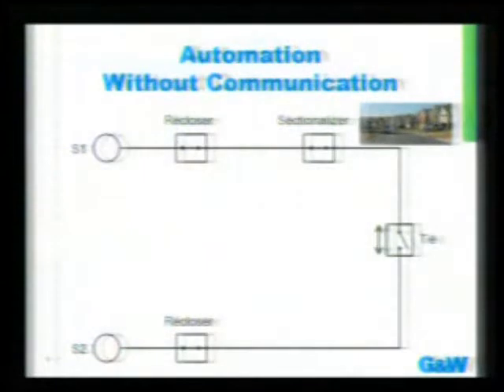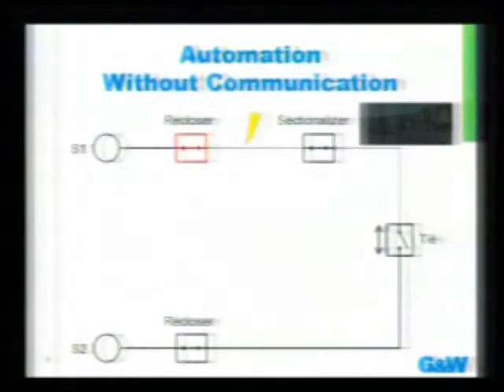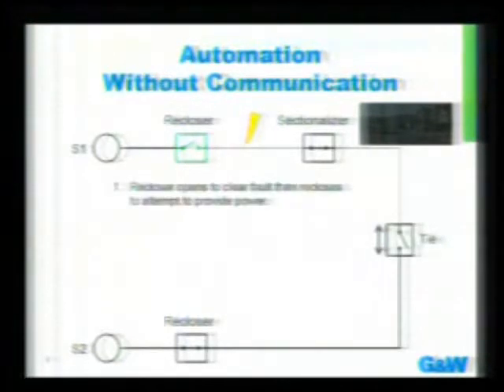This is a recloser acting as a system. This particular example is from ComEd's loop scheme logic, or automation, that we assisted them with. Now we have additional reclosers to help segment the power distribution grid. So again, we have a fault in this particular location between the first recloser and what we call the sectionalizer. That recloser will open up again, as it did before.